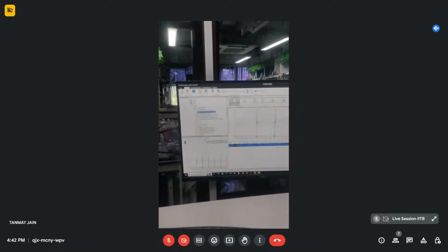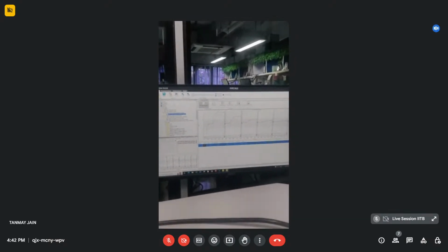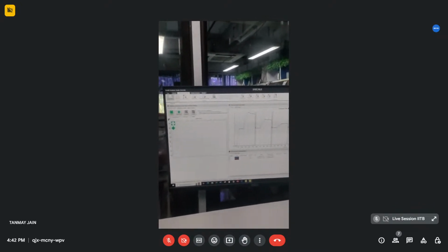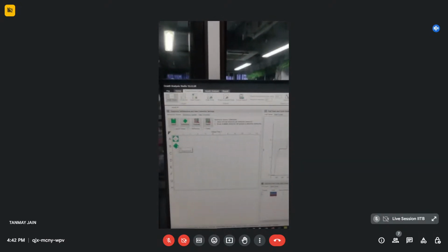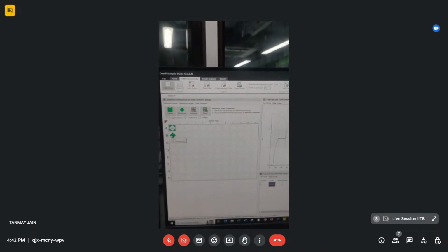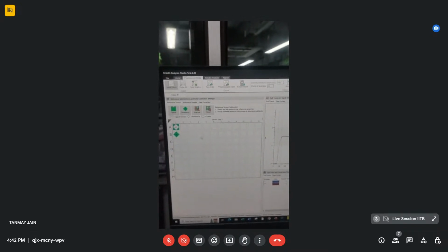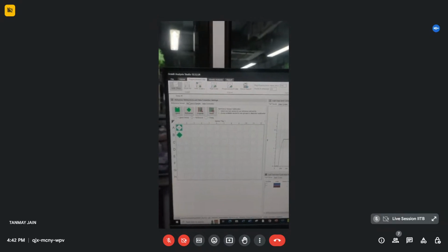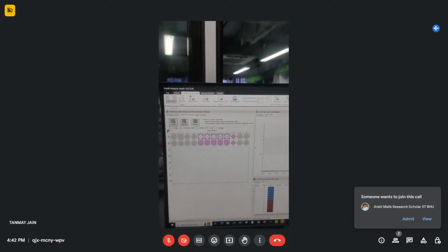As you can see, we can load up the sample here. Here we have taken a biotinylated Protein A sample on a streptavidin sensor and interacted it with IgG. Here, as you can see, this is the sensor. We can also mention which is the reference sensor, basically the negative sensor, where no ligand has been loaded, so that also gets its effect and we can subtract that. Similarly, we also keep a zero concentration analyte sample, which also gets subtracted from the other concentrations, as part of some of the data correction steps.